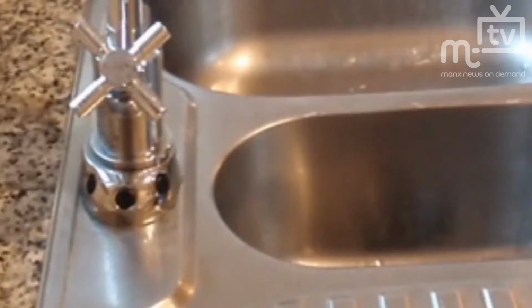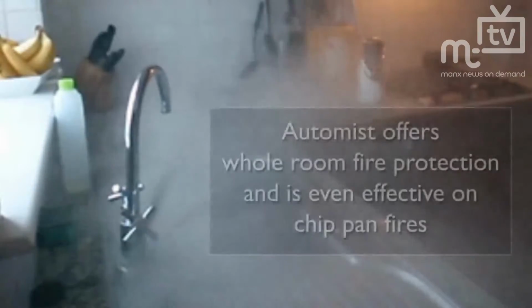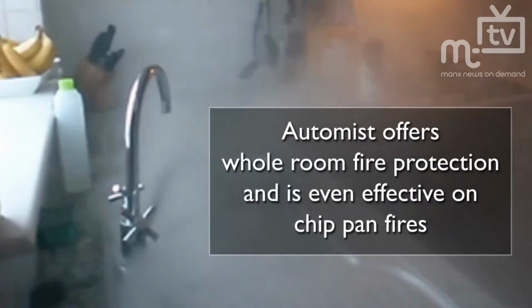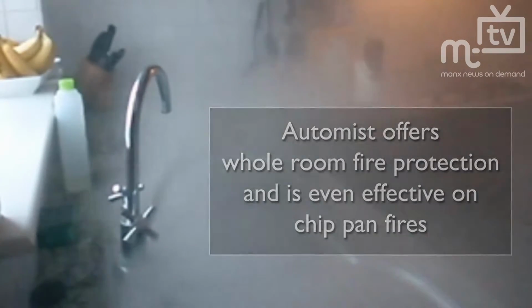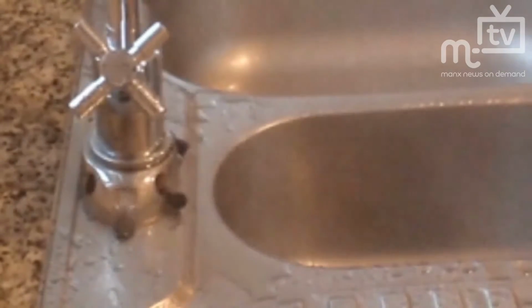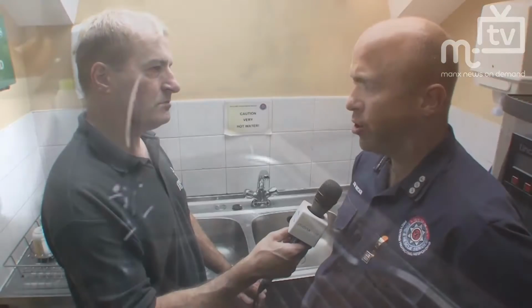Yeah. At which point the detector operates. It's got a wireless relay at the pump, which sends a signal to this, the pump activates, and basically a high water mist will appear from these two outlets at approximately 80 bar, and the system will operate at only 5 to 6 litres of water per minute. That's all it needs, and it will operate for approximately 30 minutes unless you get to the stop button, and that will basically quell and stop any fire in the kitchen. And it makes like a mist, does it then? So it's like a wall of water?